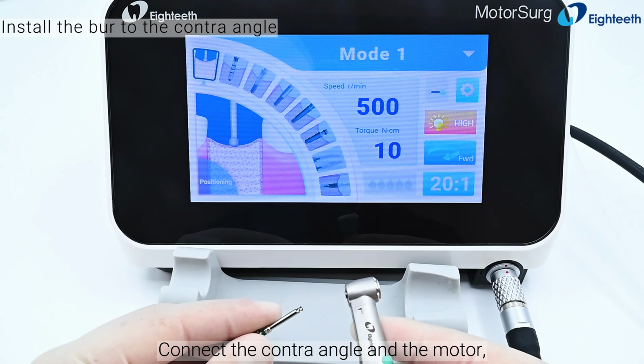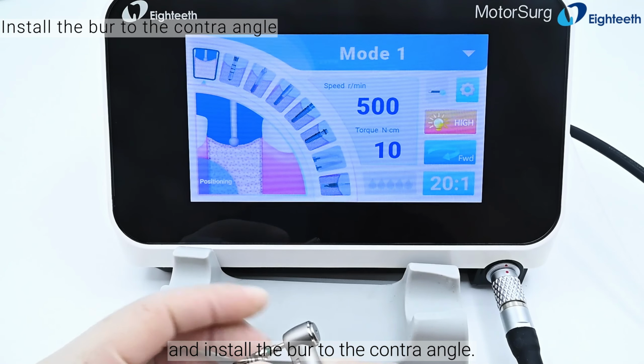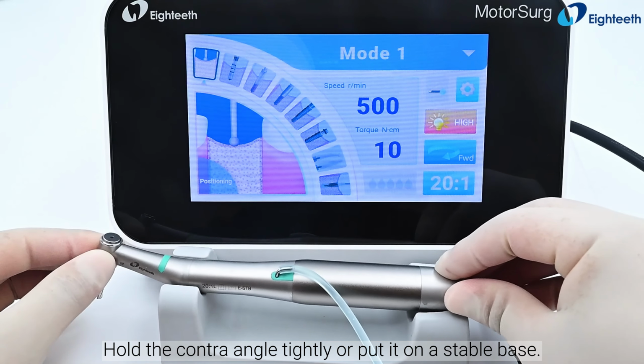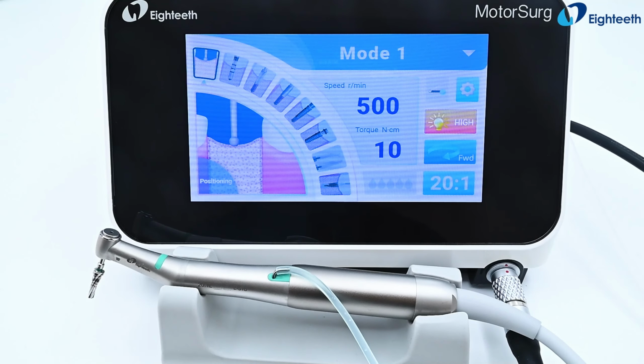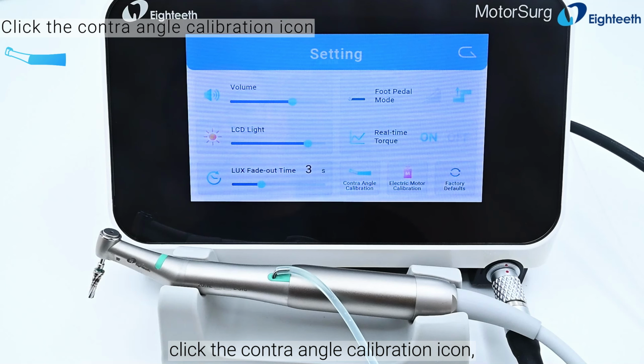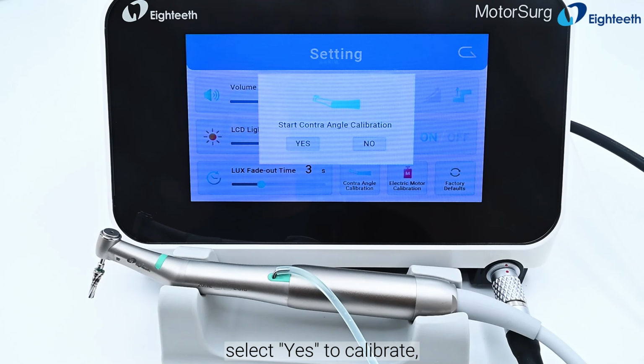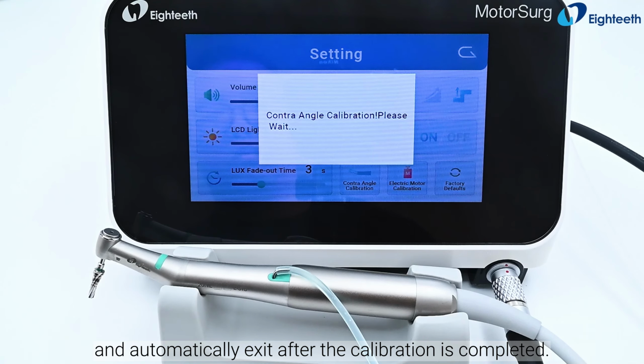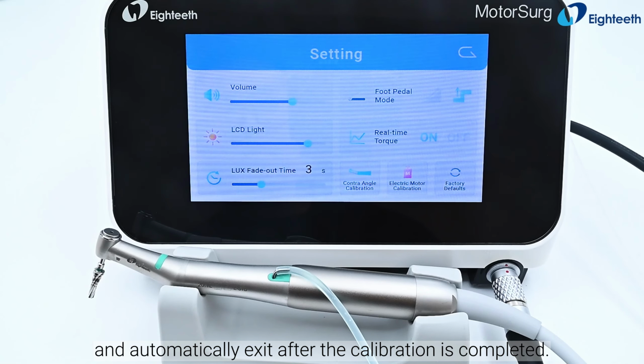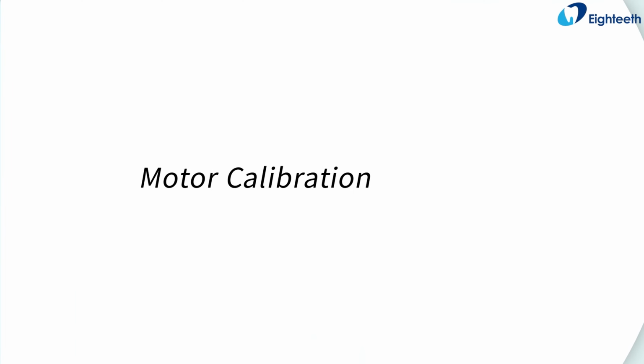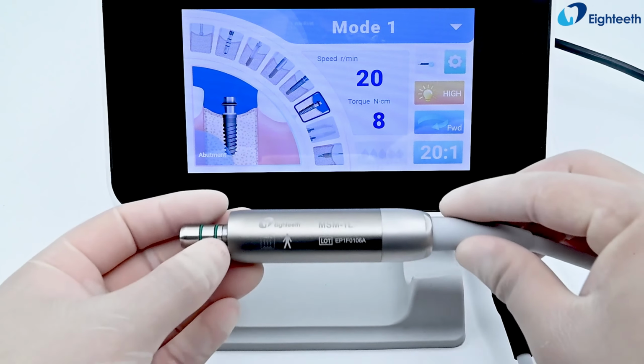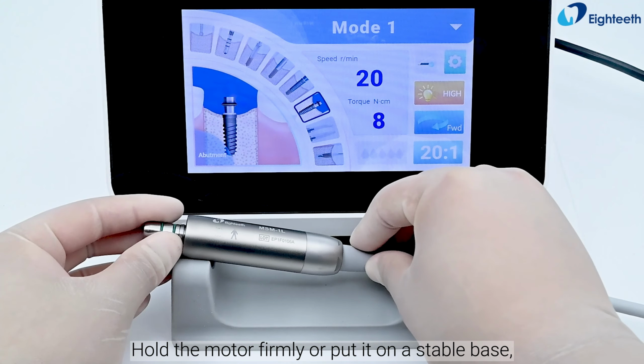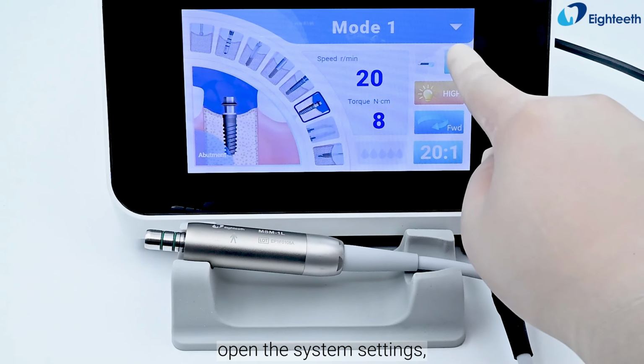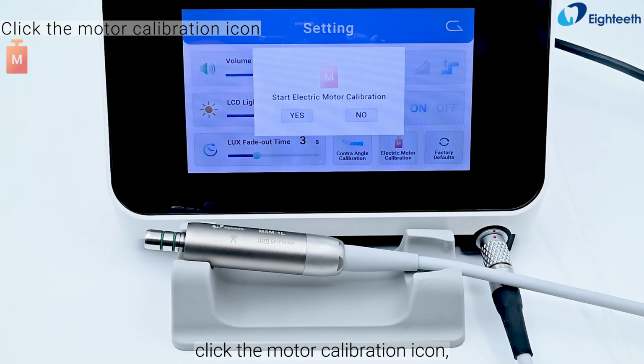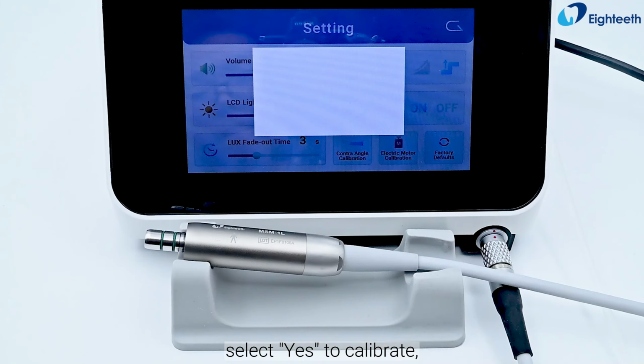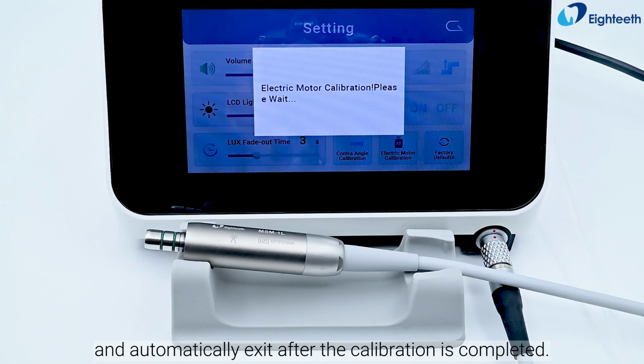Connect the contra angle and the motor, and install the burr to the contra angle. Hold the contra angle tightly or put it on a stable base. Open the system settings, click the contra angle calibration icon. Select Yes to calibrate, and automatically exit after the calibration is completed. Hold the motor firmly or put it on a stable base. Open the system settings. Click the motor calibration icon, select Yes to calibrate, and automatically exit after the calibration is completed.